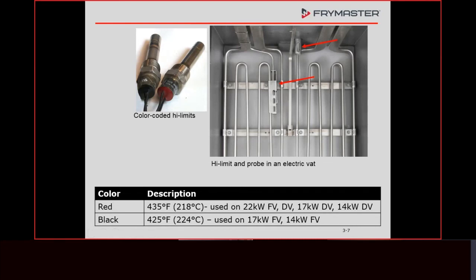So, but anyway, just make sure we have a high limit that's in place and functional. It used to be that whenever we did a startup, we always did a high limit check. That's not the case anymore, because if you went in there and did a high limit check and burned up the brand new oil, you're probably not going to be asked to come back to that store again. The only places I know that do high limit checks are the military. We get calls from them quite a bit about how to do high limit checks, but other than that, I don't know people who do it regularly. Anyway, just make sure that the high limit is intact and working.